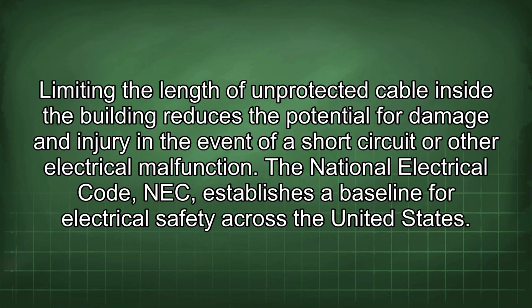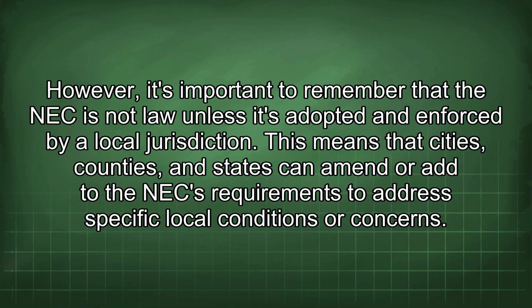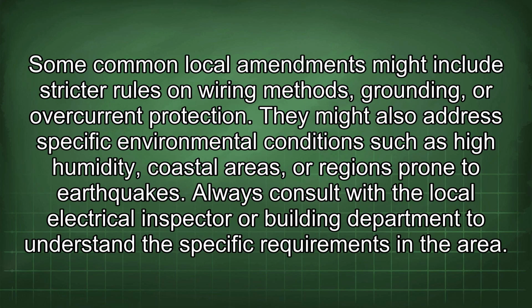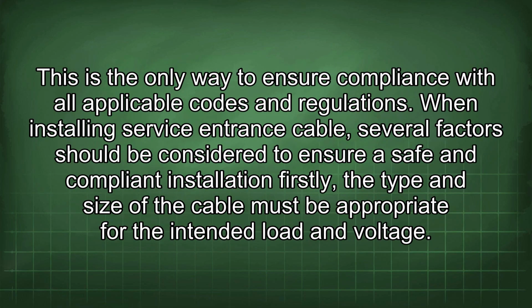The National Electrical Code (NEC) establishes a baseline for electrical safety across the United States. However, it's important to remember that the NEC is not law unless it's adopted and enforced by a local jurisdiction. This means that cities, counties, and states can amend or add to the NEC requirements to address specific local conditions or concerns. Some common local amendments might include stricter rules on wiring methods, grounding, or overcurrent protection. They might also address specific environmental conditions such as high humidity, coastal areas, or regions prone to earthquakes. Always consult with a local electrical inspector or building department to understand the specific requirements in the area. This is the only way to ensure compliance with all applicable codes and regulations.